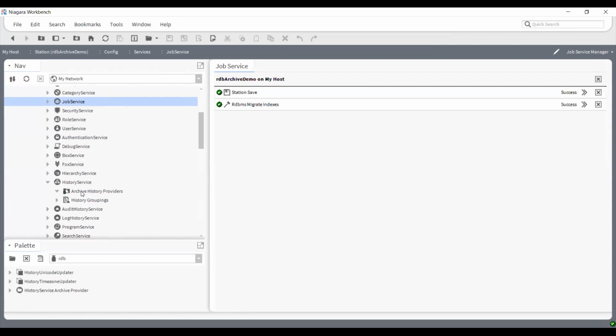We wanted to plug it in at a low enough level where any of your applications, any of the chart views, any of the history table views, series transform, BQL queries, all of those things will just work with archive data now, because under the covers, the history service is providing history records for a query to a history that's both local history records supplemented by archive history records. So that's the reason we plug it in at this level.